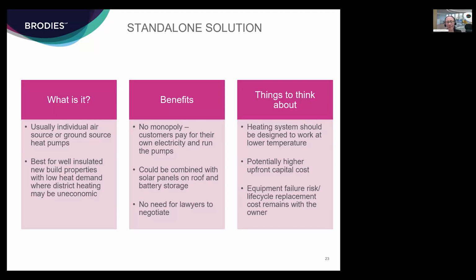In terms of things to think about, the key thing is the building type, so making sure that your heating system can work with the lower temperature heats generally supplied from a heat pump. You'd be responsible for the higher upfront capital cost, particularly until deployment increases and the cost of these heat pumps comes down. You retain, because it's standalone, the equipment failure risk, and so life cycle replacement cost needs to be considered too.